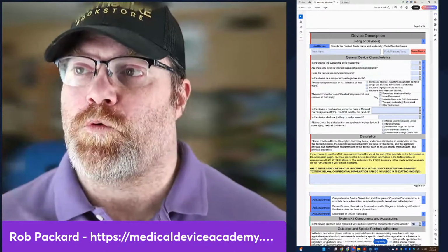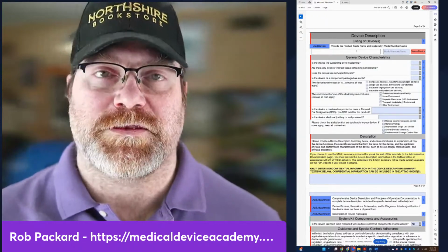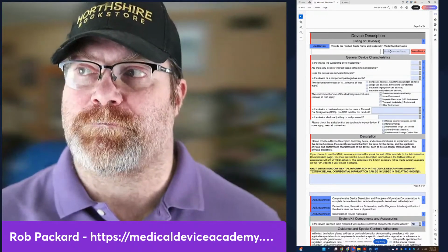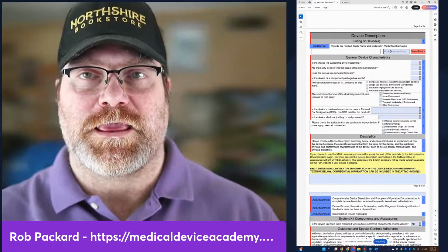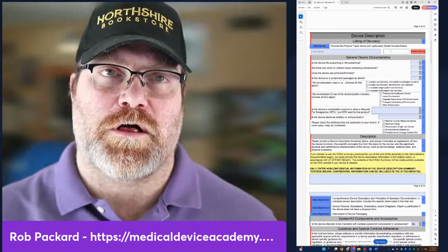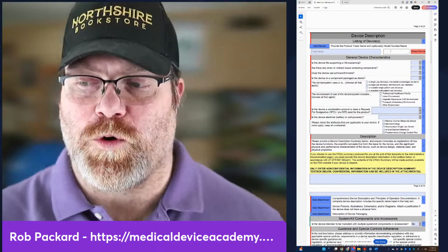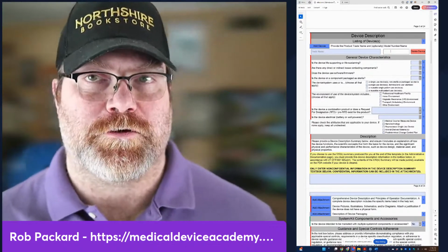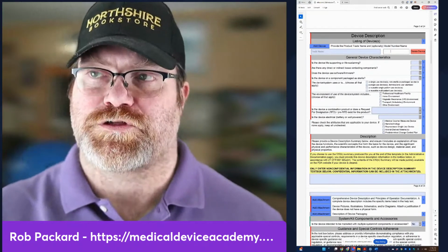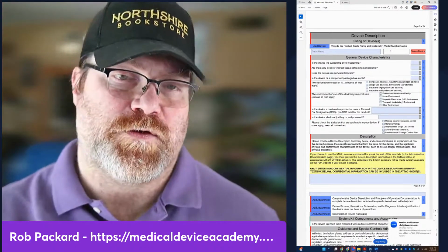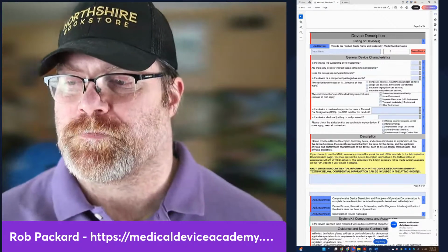But one of the first things we put in this device description section is the name of the device, so that's the trade name, and then a list of the models. So you'd put those there. And those will be duplicated in your indications form, or FDA Form 3881. It also is going to appear in your declaration of conformity and a couple other places. But you should have a list of all your models. So you could have a very long list there if you have a lot of different sizes, like sutures, where you might have 20 different sizes in a submission.